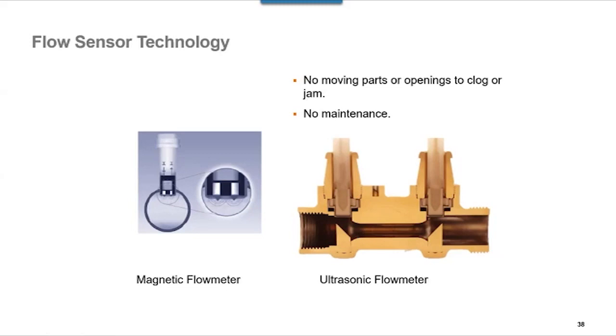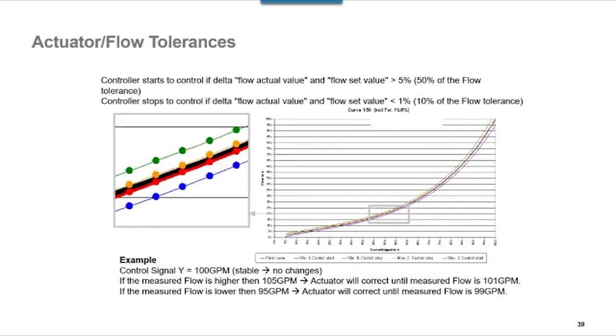Because the whole idea of the magnetic flow meter is that the flow is measured by changes in an induced voltage that's generated by this conductive field. So the fluid needs to be going across it at those 2 points. Again, there's a lot of product out there that has that. You're not going to see it on new product anymore today. This is just a pictorial to show you the whole concept.